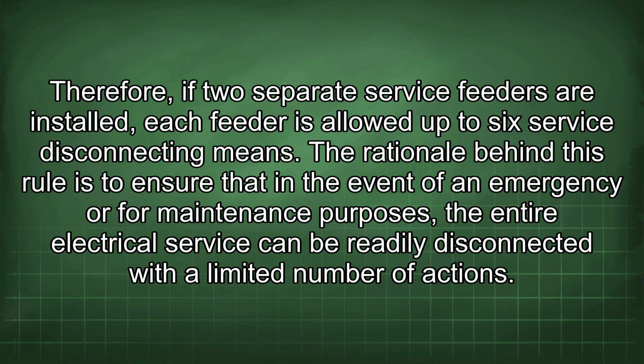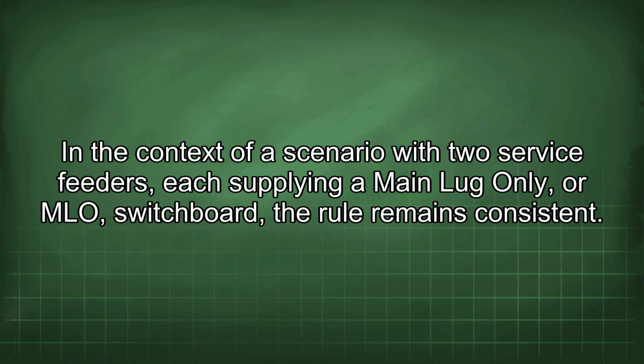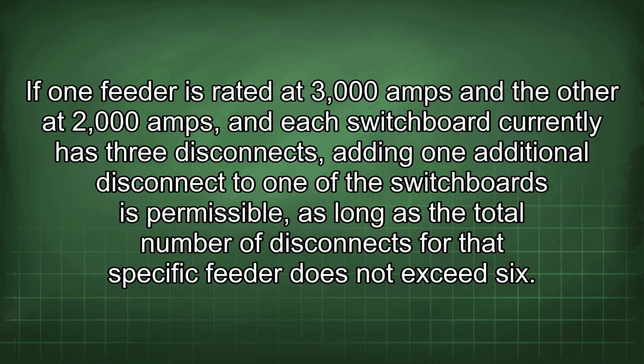The rationale behind this rule is to ensure that in the event of an emergency or for maintenance purposes, the entire electrical service can be readily disconnected with a limited number of actions. In the context of a scenario with 2 service feeders, each supplying a main lug only, or MLO, switchboard, the rule remains consistent. If one feeder is rated at 3000 amps and the other at 2000 amps, and each switchboard currently has 3 disconnects, adding one additional disconnect to one of the switchboards is permissible, as long as the total number of disconnects for that specific feeder does not exceed 6.